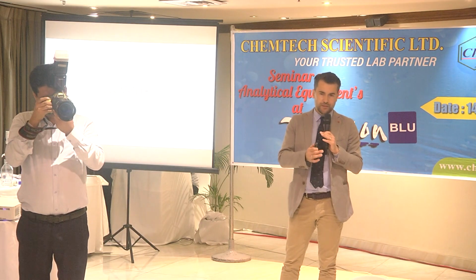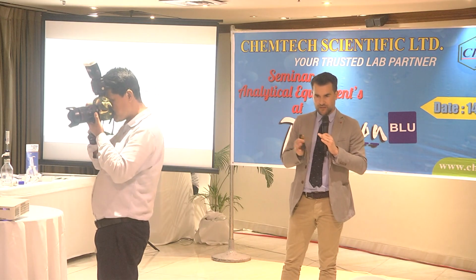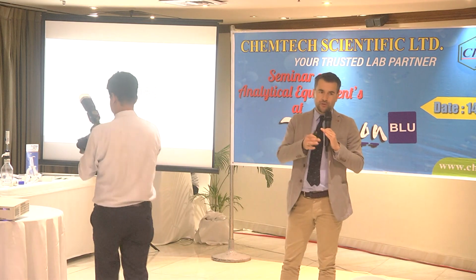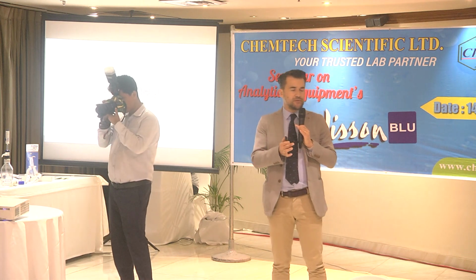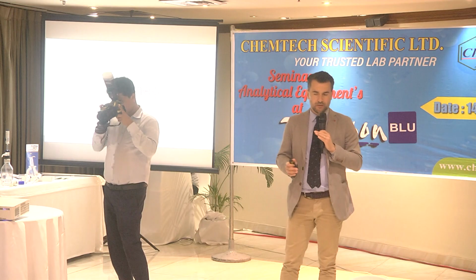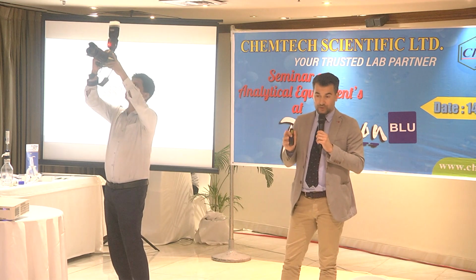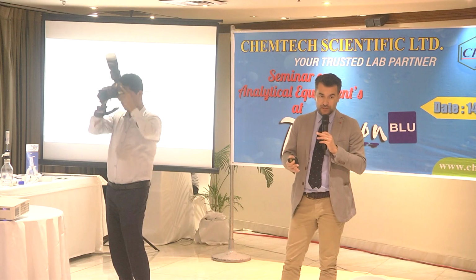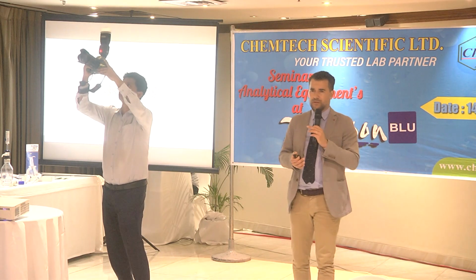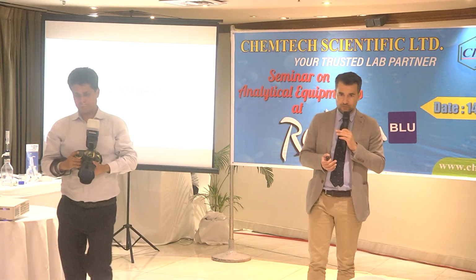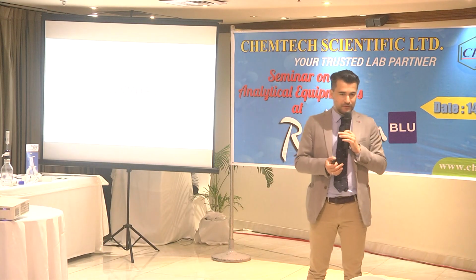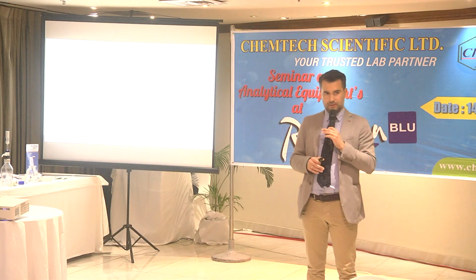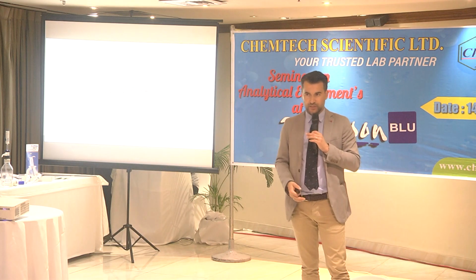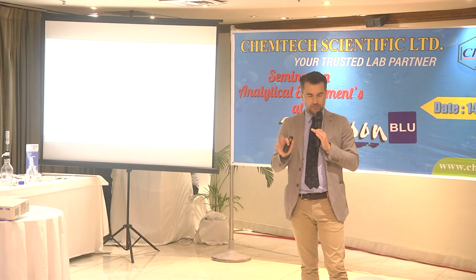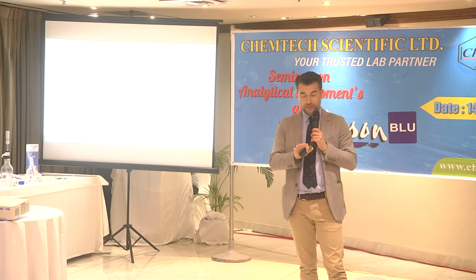For the basic model, not 10 years because the memory is too small, but for many months, depending on how many alarms. This is why I'm not telling you one month or two months, because it can be a lot of alarms. For the big screen, we have up to 10 years. We have something like 14 or more different alarms that we can set up and check. So all the alarms are downloadable.